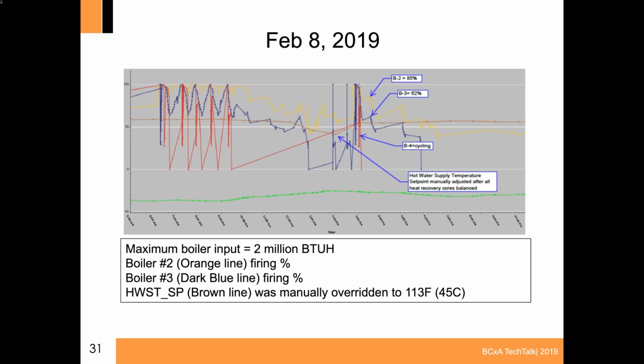There are 4 boilers in Saskatchewan because of how cold we get. We have what they call an N+1 design requirement, where if you design your building and you need 3 boilers, you've got to have a 4th one in there just in case one fails. So this is an N+1, and we have 4 2 million BTU per hour boilers, or 8 million capacity if all 4 were firing.